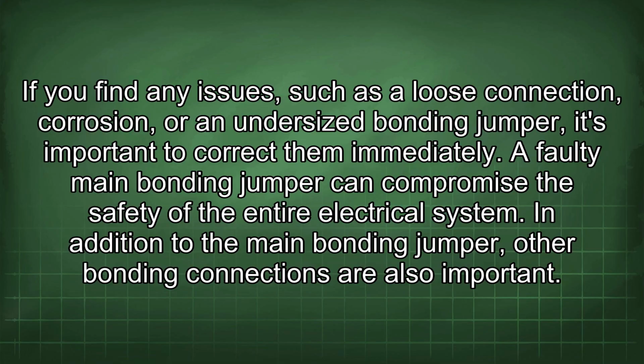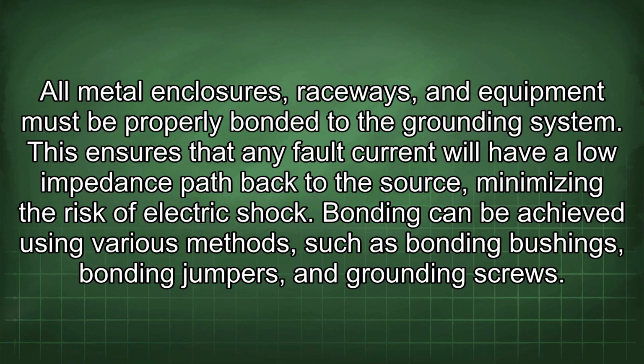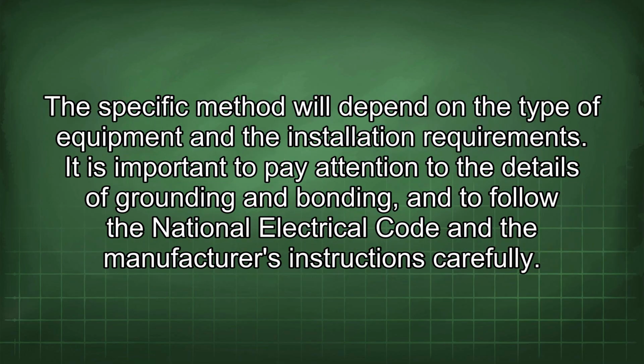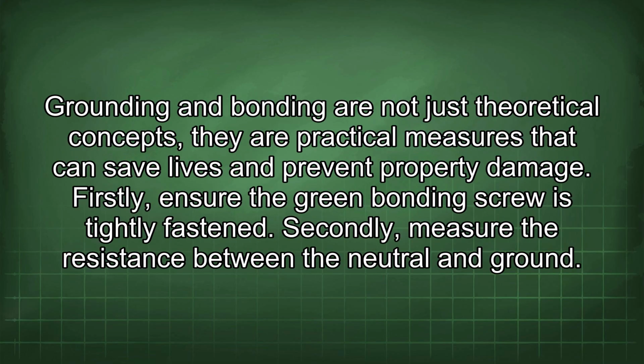In addition to the main bonding jumper, other bonding connections are also important. All metal enclosures, raceways, and equipment must be properly bonded to the grounding system. This ensures that any fault current will have a low impedance path back to the source, minimizing the risk of electric shock. Bonding can be achieved using various methods, such as bonding bushings, bonding jumpers, and grounding screws. The specific method will depend on the type of equipment and the installation requirements. It is important to pay attention to the details of grounding and bonding and to follow the National Electrical Code and the manufacturer's instructions carefully. Grounding and bonding are not just theoretical concepts, they are practical measures that can save lives and prevent property damage.